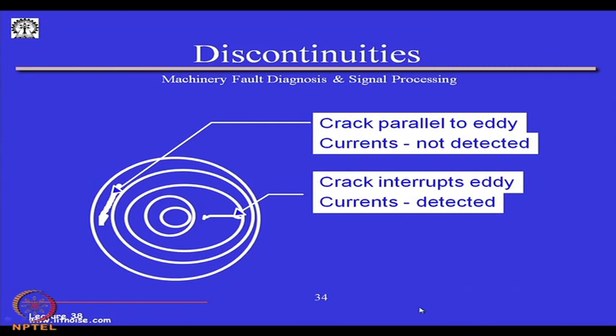Certain things to note: from the top view, if cracks are parallel to the eddy currents, no eddy current disturbance will be detected because they are not interrupting the eddy currents. If the cracks are in the cross dimension, the eddy currents are disturbed and you will get a signal.